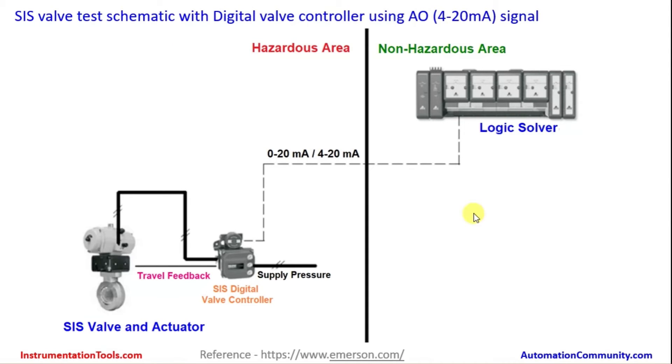Here we go over a photograph about the digital valve controller arrangement. This is the SIS valve test schematic with the digital valve controller using an AO (analog output) which is a 4 to 20 milliamp signal from the safety instrumented system logic solver. There are different types of modules: analog input, analog output, digital input, digital output, and some communication modes. In this arrangement, the 4 to 20 milliamp analog output signal goes to the valve and the digital valve controller, which can be used to stroke and test the travel feedback — how much the valve traveled — all measurable from the same device.